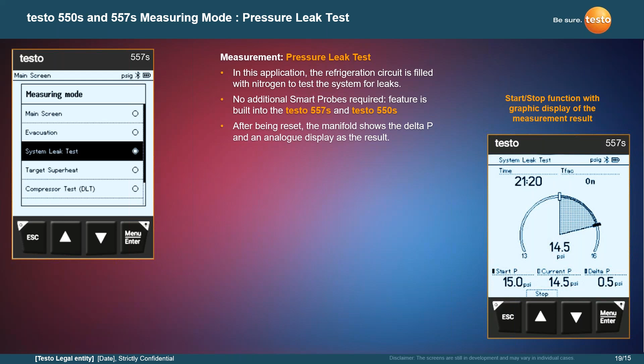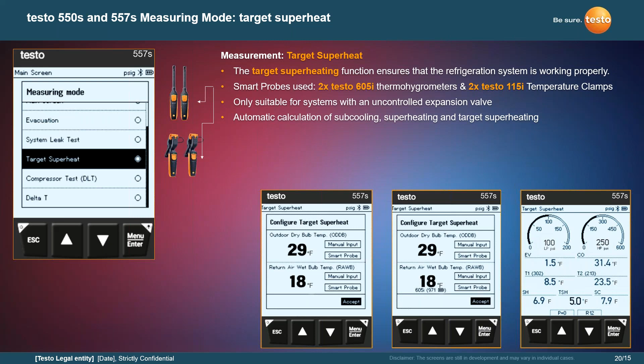Target superheat. Now, target superheat is a specific type of superheat reading that you get by taking the indoor wet bulb and outdoor dry bulb, and this would be much more accurate at getting your superheat reading, and this is what you want to do. So this is in our system. This is an application side to both the manifolds and our smart probe application as well.